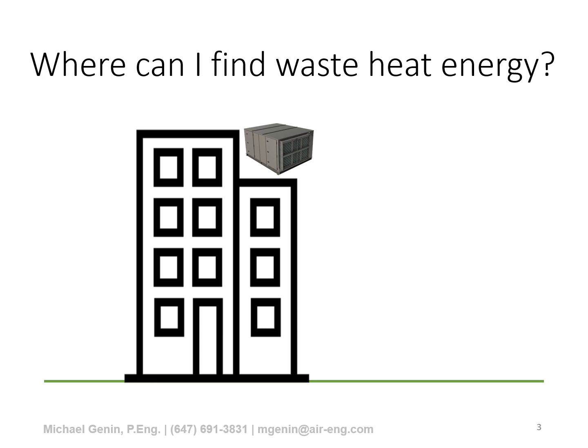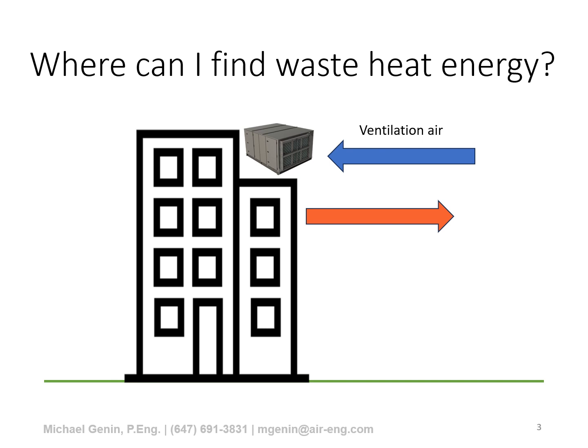So where can I find waste heat in the building? The first area we're going to look at is in the ventilation system. We bring fresh air into a building or process. We have to exhaust a similar amount of air from that building. And so is there an opportunity to recover the energy between the two airstreams? The second part is recovering energy within the building. Buildings, primarily larger ones, will have multiple zones, and some zones may be in cooling and some zones may be in heating. So is there an opportunity to recuperate the heat between different zones of the building to reduce our heating load?